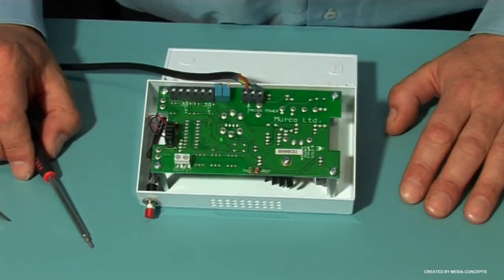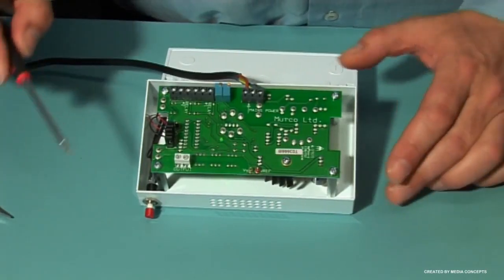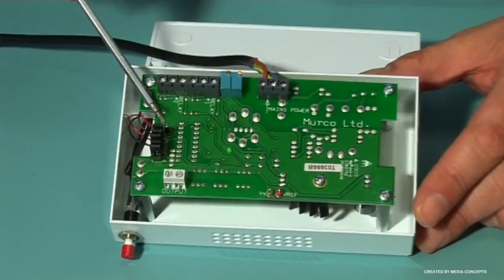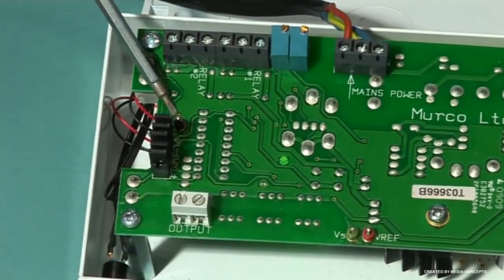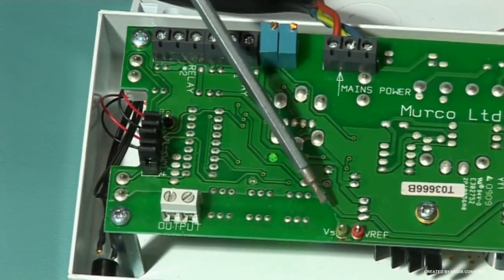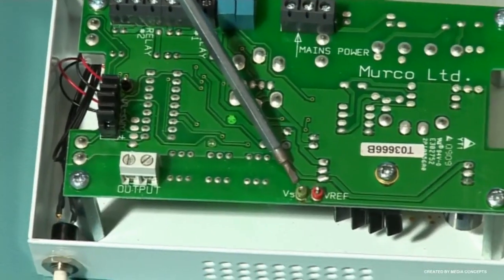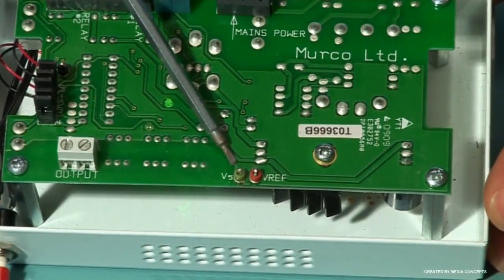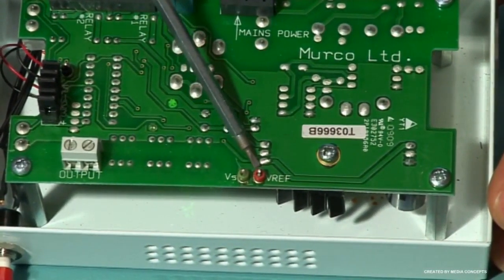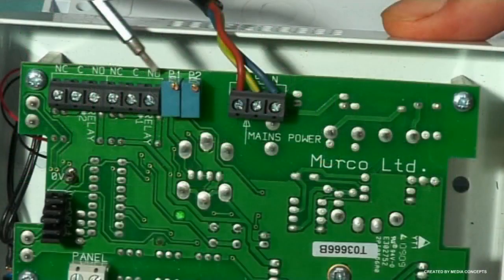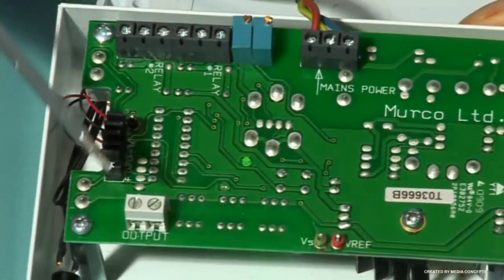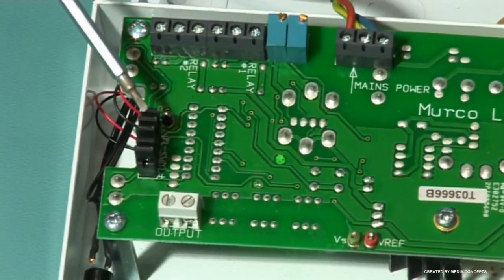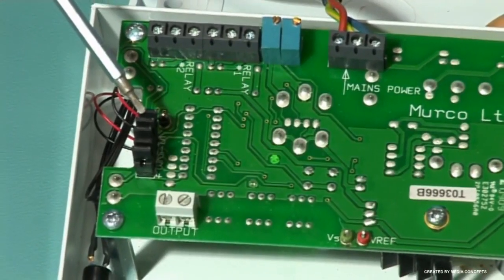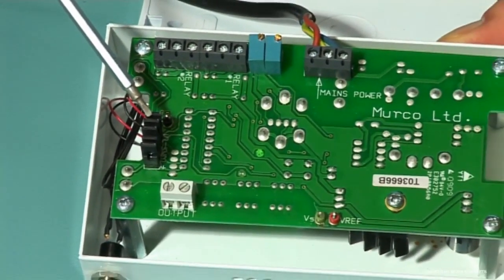The 0 volt test point is marked here on the board as 0V. The standby voltage output in clean air is measured as Vs, and the voltage output on alarm is measured at Vref. The adjustment for standby voltage is done at P1, and the alarm set voltage adjustment is done at P2. The delay settings on the unit are on header HD1 as shown here. The jumpers are normally red or black in colour.